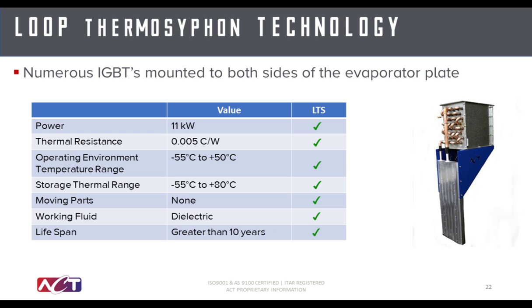The power needed to dissipate was in the 11 kilowatt range, with an operating temperature from negative 55 degrees Celsius to positive 50 degrees Celsius. There was a need for dielectricity of the working fluid, for a lack of risk of failure with no moving parts. A loop thermosiphon approach satisfied all these requirements and tested optimally for this customer.